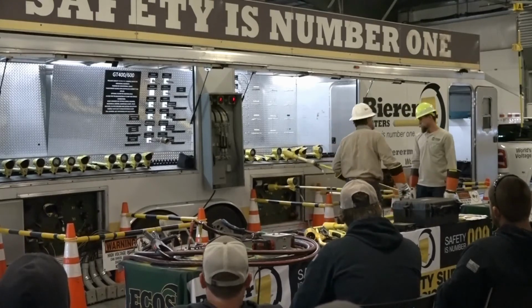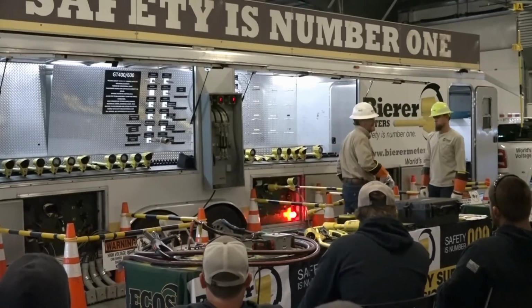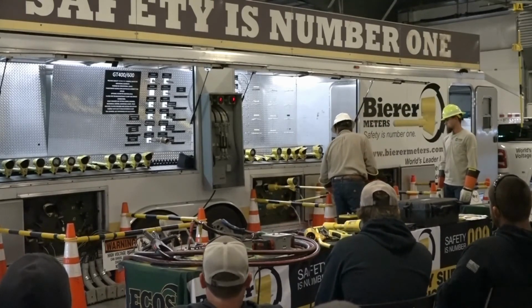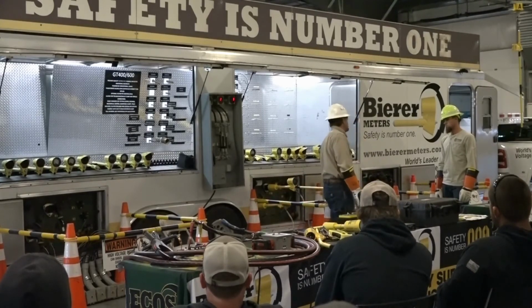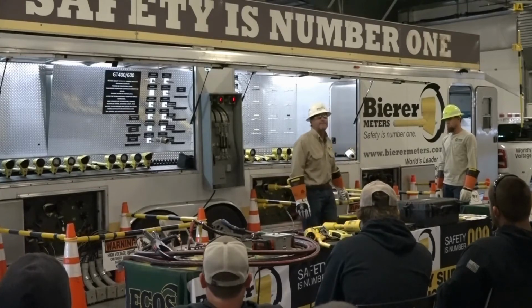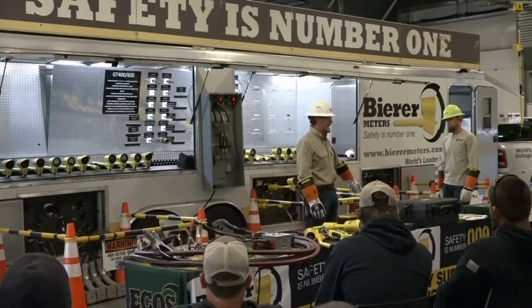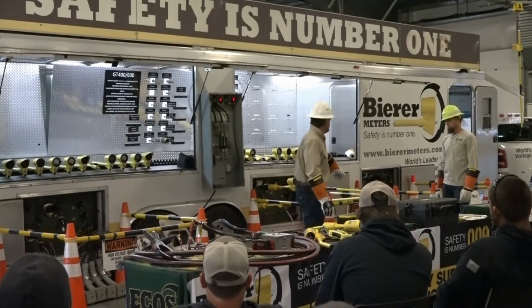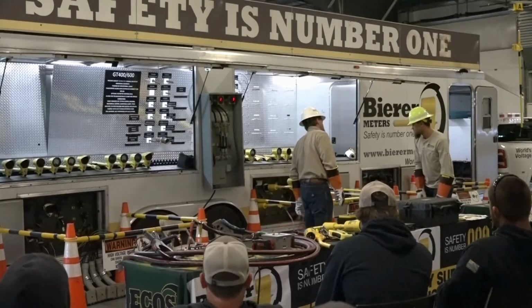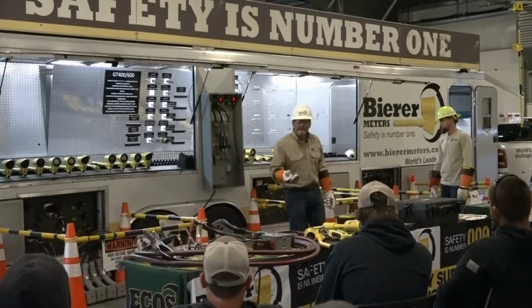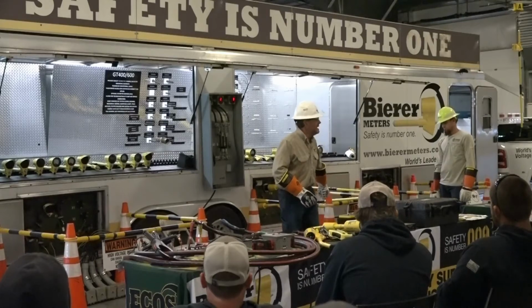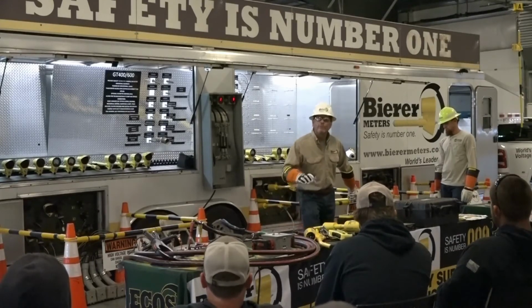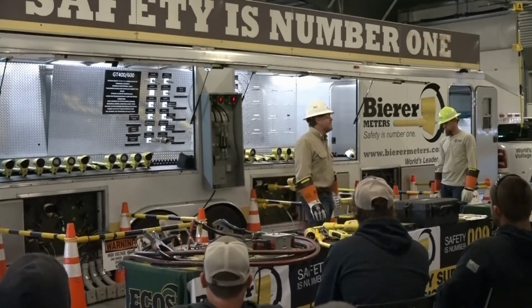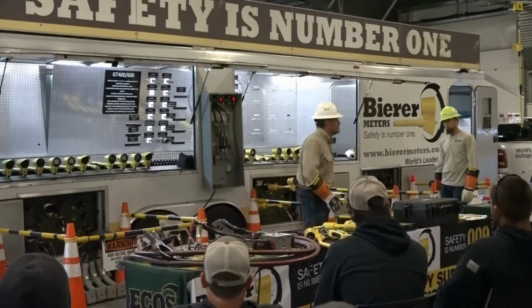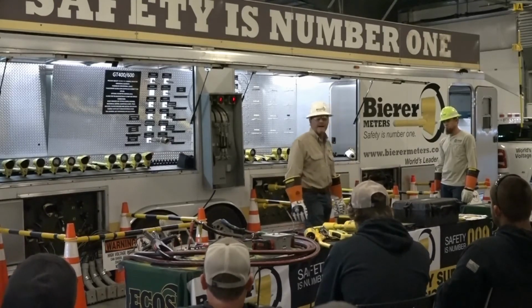Now I'm going to go to the other side of the cabinet. We're going to see if we're in phase or out of phase. I go to the other side of the cabinet, overhead line. There's about a 0.5 milliamp that actually flows through that cable right now. What's your reading? 0.2, there's a little bleed on that cable. Hear the buzz? If this cable was laying in wet grass, it would probably show a 0.6, more of a bleed if it was wet grass.